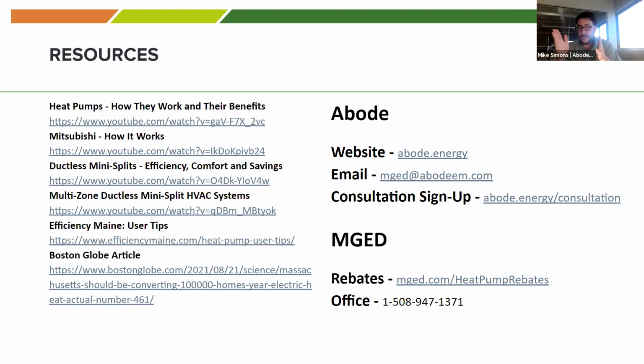Thought number 1 is thinking back to that curve of how many hours we spend in the coldest of cold days, like the design temperature. It's only 10% or 15% of the hours of the winter. So you could make up that delta by installing an electric heat kit on top of the heat pump. The heat pump's still putting out 55,000 BTUs per hour, and then that electric heat kit could put out potentially 25,000 additional BTUs per hour on the coldest of cold days, or anytime it's below 20 degrees or 15 degrees. It really depends on the home.